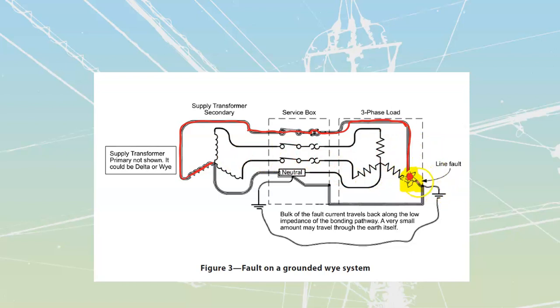Well, it's just the same as you and I. It's going to try and take the easy path, which is going to be a low impedance path. See the resistance here? We don't have that type of resistance here on our bonding path. So it's going to divert to our bonding path, and then from there is going to carry the bulk of the current back along the bond, back up to my neutral. Once it hits the neutral, it is then going to return to the transformer. Do you see that red line? It is a complete path over there.